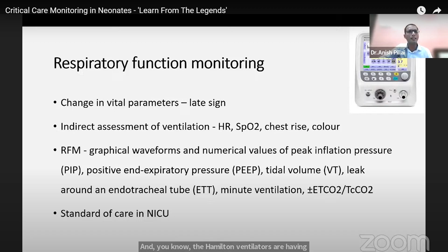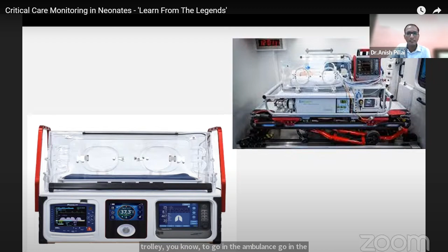And that is the standard of care in the NICU, right? We use a respiratory function monitor for all babies on a ventilator. They will all have this display for us. So why not use it in transport? A lot of the newer transport ventilators, Acutronic and the Hamilton ventilators, have a respiratory function monitor. And there are also some indigenous monitors that are being designed for transport use only. This is the Hamilton system, which is very popular in North America. You can see that it has a very clear respiratory function monitor. It has EtCO2, it has a continuous temperature display, and it can be mounted on a trolley to go in the ambulance, go in the NICU. So it can travel everywhere, along the lift.